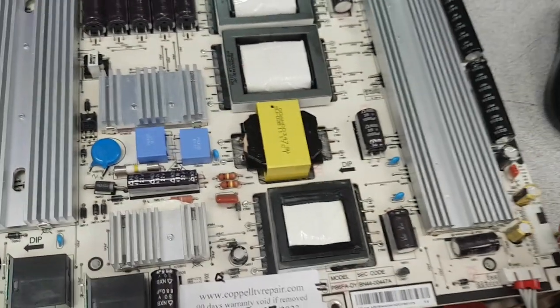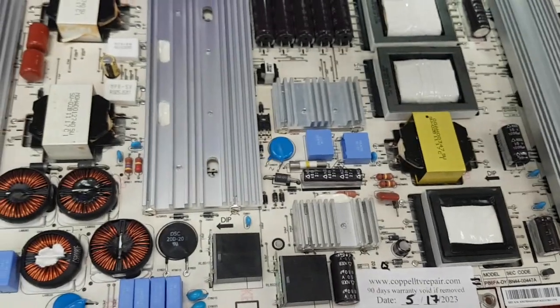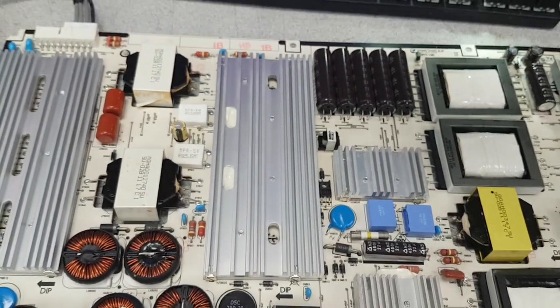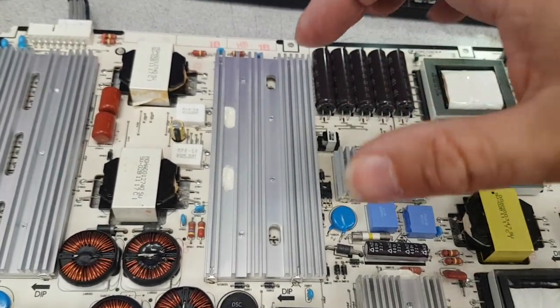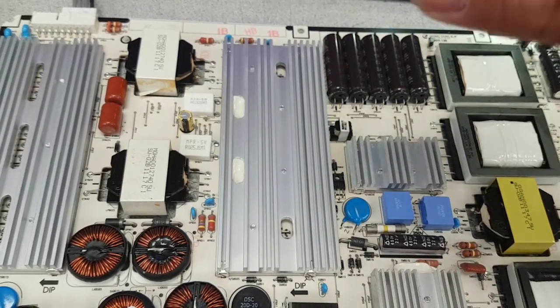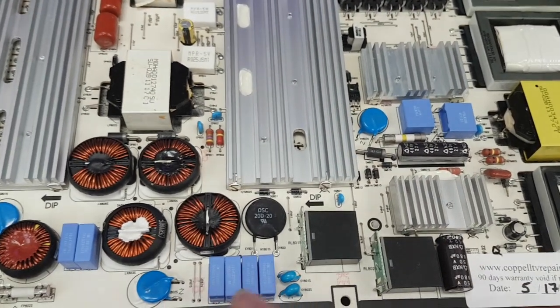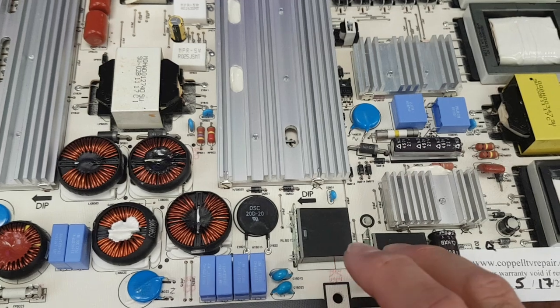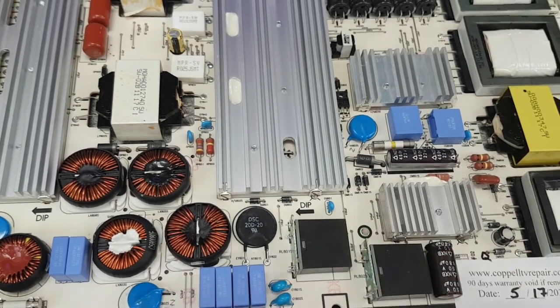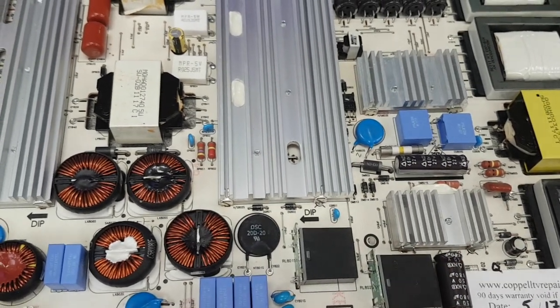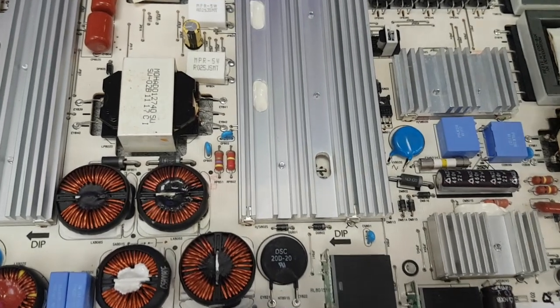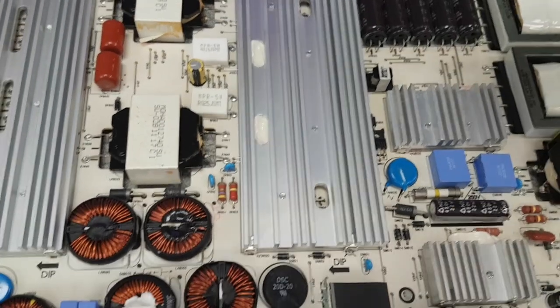The second thing that board does is usually conditional upon release. There is a little circuit that detects whether the 400 volts come up or not, and when they do, the second relay closes here. One of them closes as soon as this is passed, the other, once this is raised up, closes the second relay.